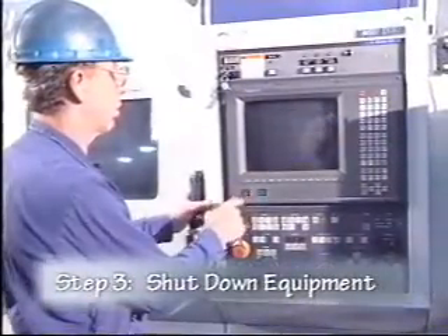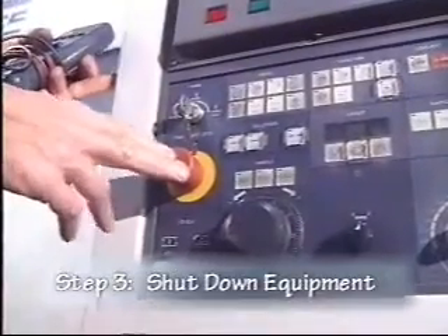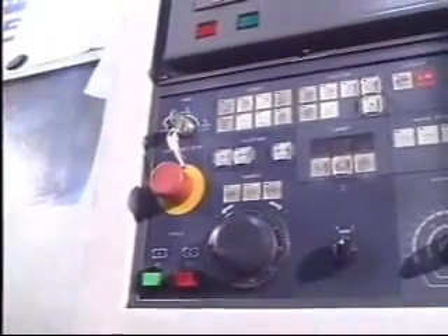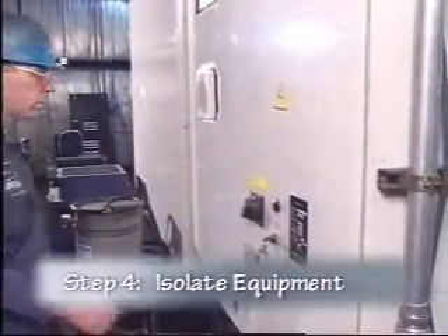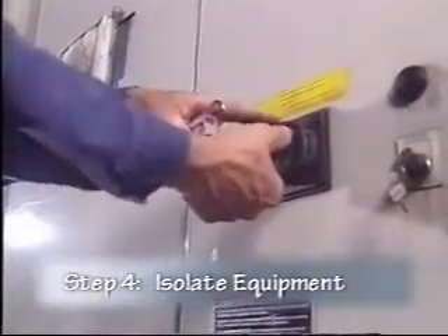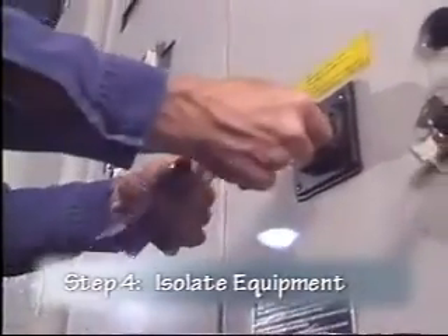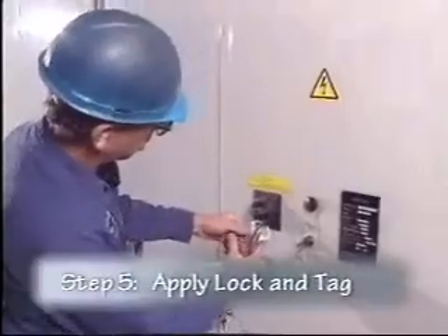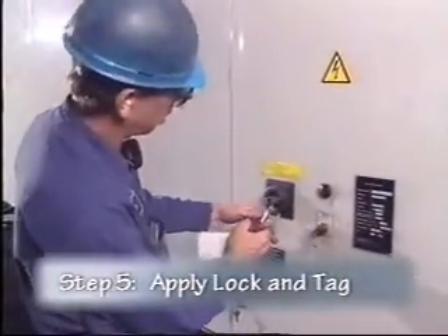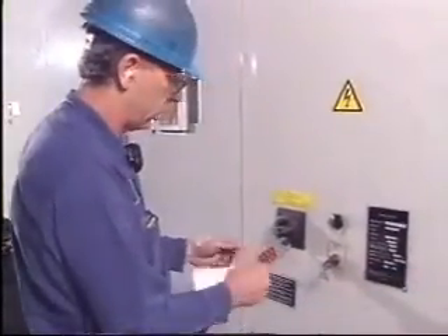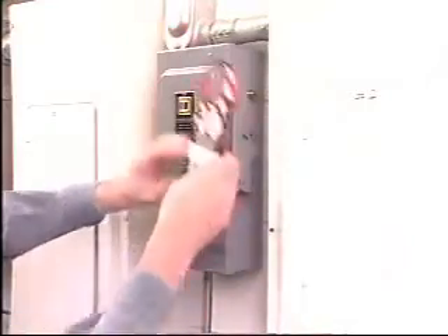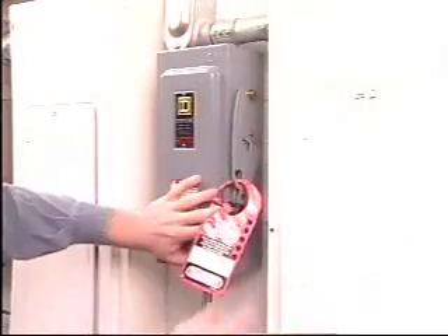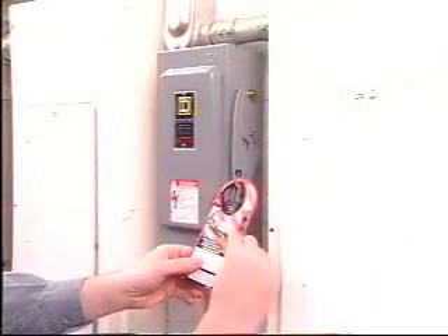Step 3. Stop the equipment by using its normal shutdown procedure. Step 4. Isolate the equipment by turning off the energy at the main power source. Step 5. Apply a lock to the energy isolating device. The lock or the tag that goes with it must clearly indicate who applied the lockout device.